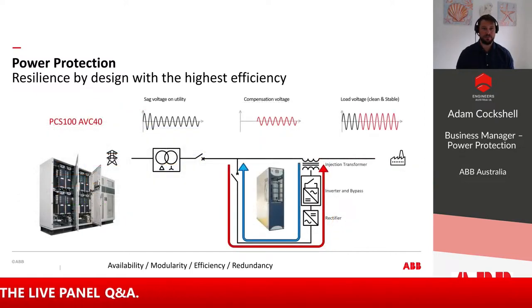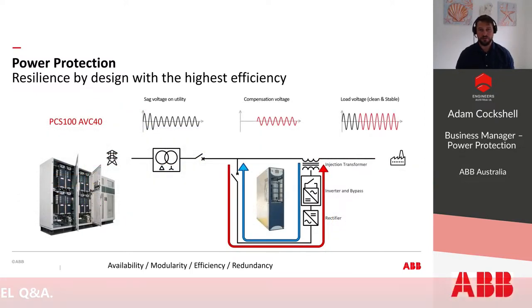ABB's PCS100 AVC40 active voltage conditioner is a converter-based voltage regulation device that can be connected between the main supply and sensitive electrical equipment or machinery to protect against supply anomalies, ensuring a clean, stable voltage and providing instant voltage sag and surge correction, ensuring maximum productivity. Through ABB's bidirectional PCS100 converter modules, a compensating voltage is either injected or absorbed with respect to the event experienced.